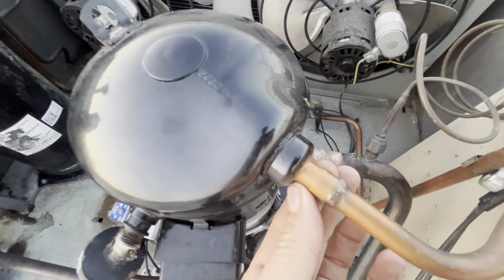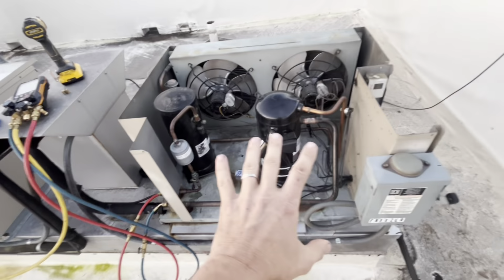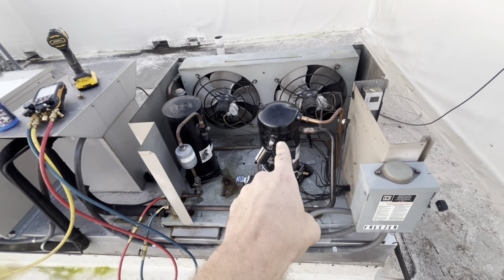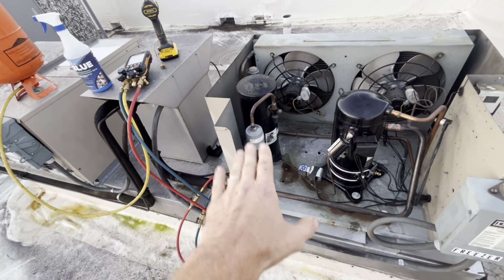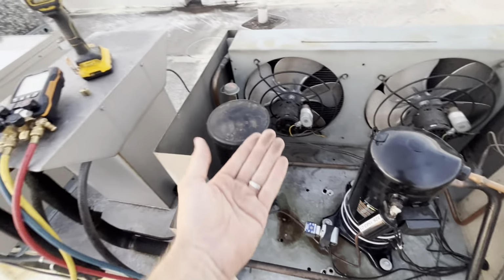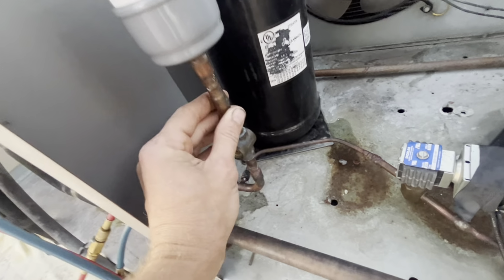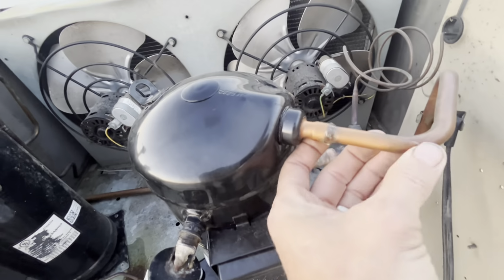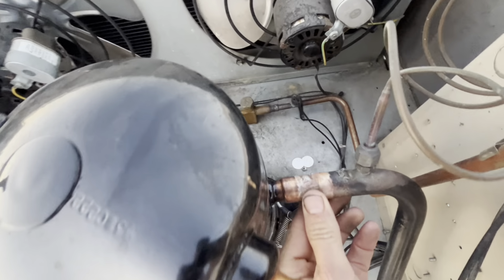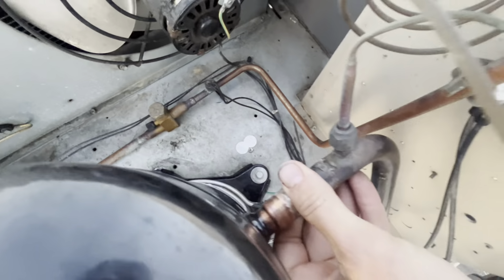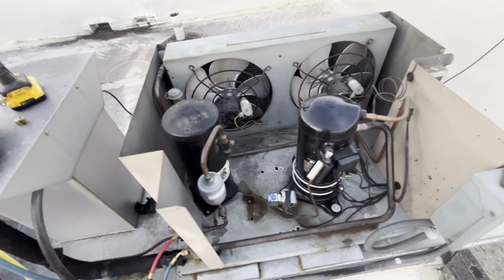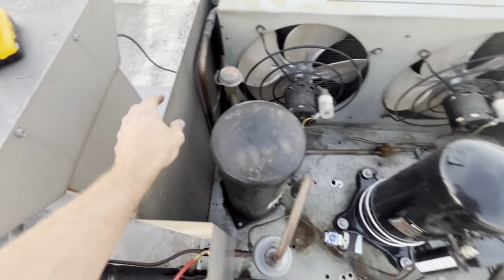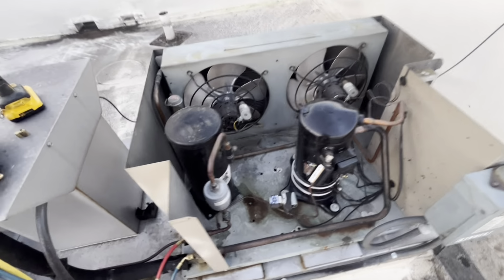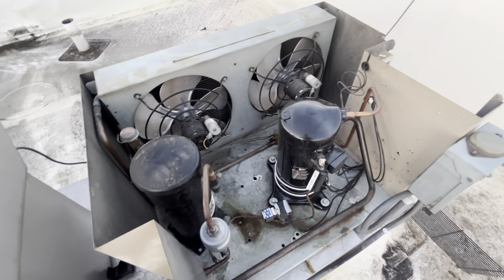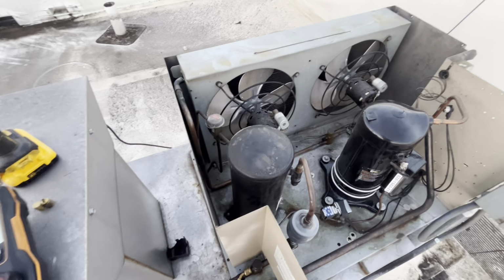But also just skimming through, right? When I changed this compressor, 1, 2, 3, 4, 5, those are my connections. Everything is real dry and dusty up here, and to be honest, at all my connections too. So I don't see an immediate "oh no." I pulled a good vacuum on it, so it didn't have a leak at the time. But stranger things. So I'm gonna soap it up.